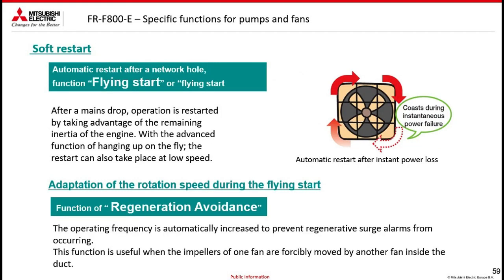A further very particular function is the flying restart. It is useful because after a power failure, the rotation is restarted by exploiting the remaining inertia of the motor. In doing so, it does not stop the motor to restart. Just think of a very large fan. It would be unthinkable to have it stop completely and then start again from zero.